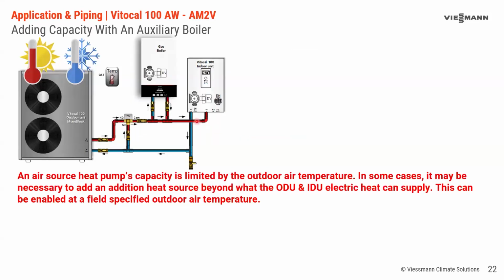In some instances, we may not have enough energy all the time. An air source heat pump of any kind, air to air, air to water, as the outdoor air temperature changes, the heat pump is going to have capacity changes. As it gets colder outside, we're going to have less ability to pull heat out of the outside air. And even on the other side, on the positive side of this, the hot side of this, once we get up to a certain ambient outdoor temperature, it's hard to reject the heat because the ambient around it is hot. So we have to look at this scenario from a heating perspective.